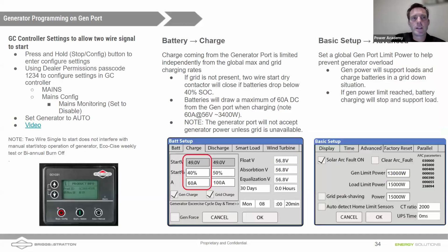Point out some of the settings for generators. So if you are using a generator that's normally an auto main sensing generator, like our generators, you'll want to disable auto main sensing.